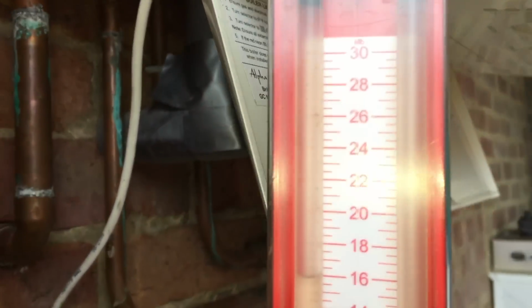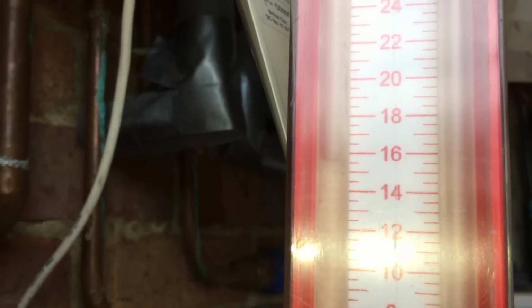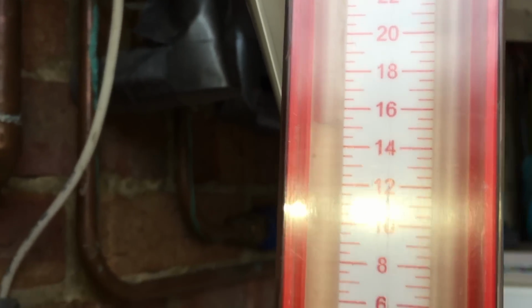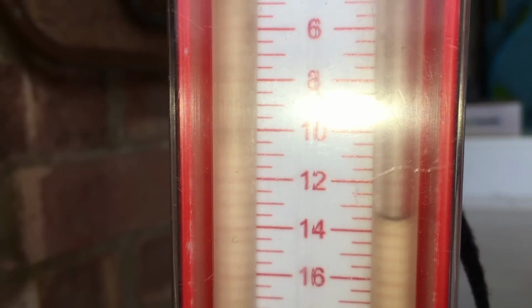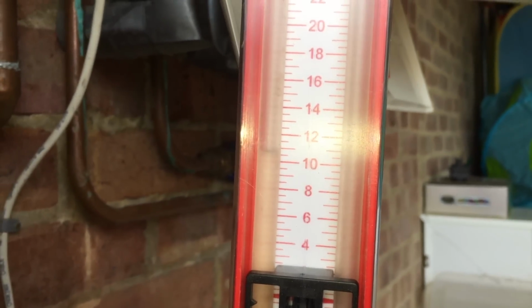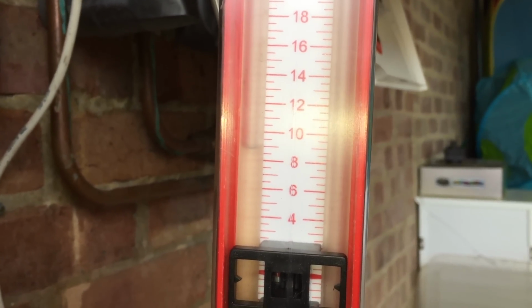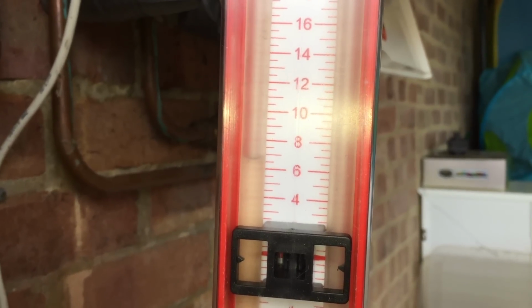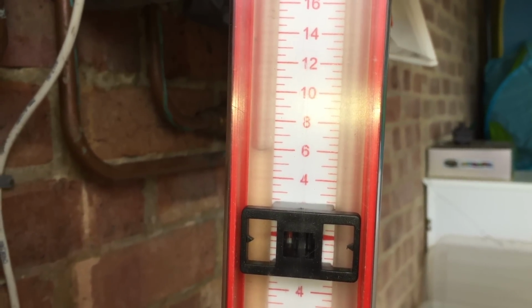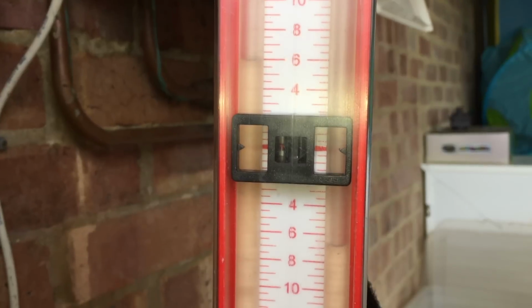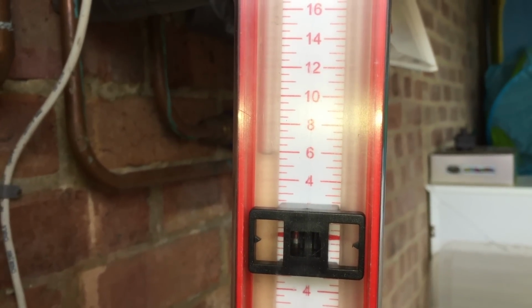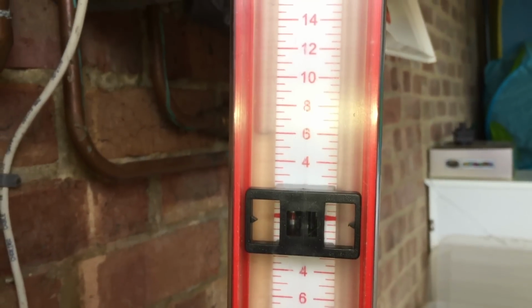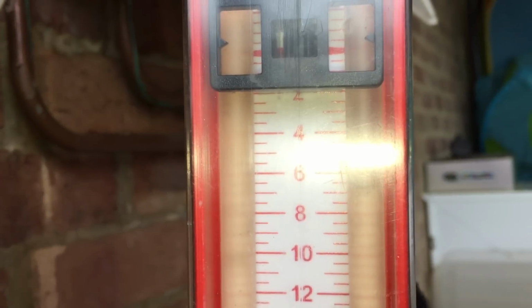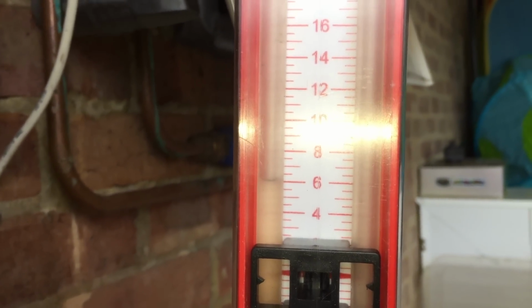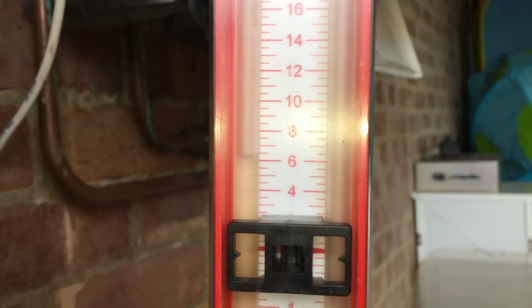Oh, well, ain't that a problem. Inlet pressure right now is 16 millibar, and this isn't even fired, really. Let's drop in as the boiler starts to ramp up. 10. Do you think we might have found our problem? Do you think maybe 6 millibar inlet pressure might not be adequate? Well, okay, it's not quite 6, it's 6 1/4 because we've got 6 1/2 there and 6 there. Do you reckon that might be causing the problem?